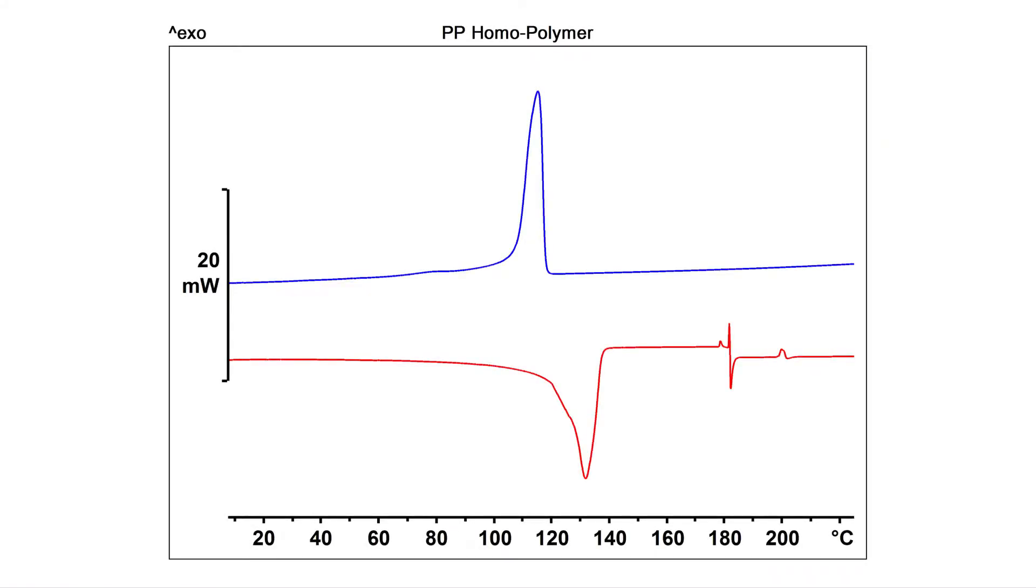Environmental factors, such as weather conditions or road traffic, can trigger changes in ambient temperature or pressure. Also, electronic devices such as mobile phones may cause artifacts on the measurement curves. These factors show up as artifacts on the DSC curve.